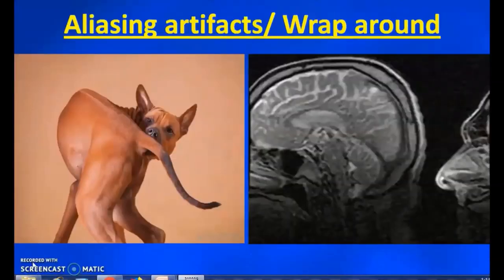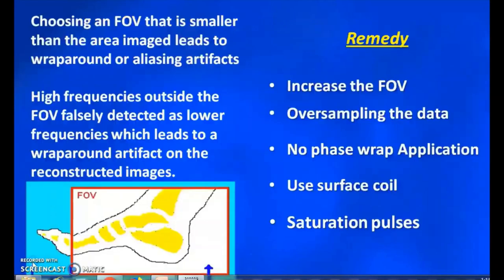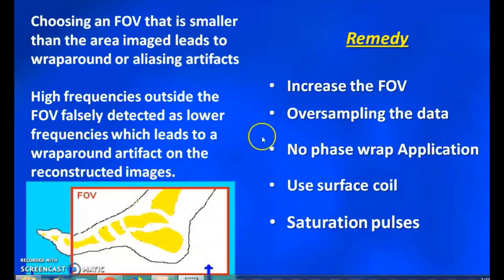The final artifact is the aliasing or wraparound artifact, which commonly happens when choosing a small FOV. The region from outside the FOV gets wrapped around to the back side of the area. This can be removed by increasing the FOV, using surface coils, or applying saturation pulses to remove this kind of artifact.